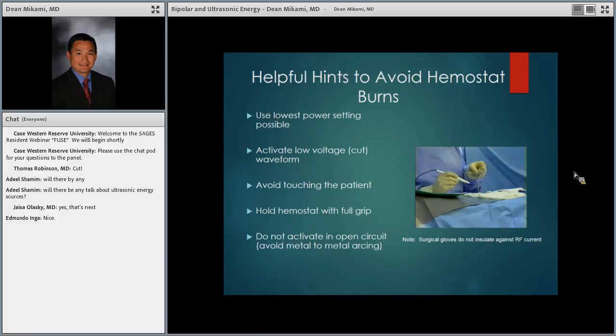So when you do that, you're going to cause arcing or a vaporization effect if you're using cut, and the current will jump off the end of your active electrode to your hemostat, creating this very high energy level right off the bat, and that could cause you to burn yourself. So you want to touch the instrument first and then activate the active electrode, so you don't do open air activation. And that will definitely decrease the chance of you getting a hemostat burn during surgery.